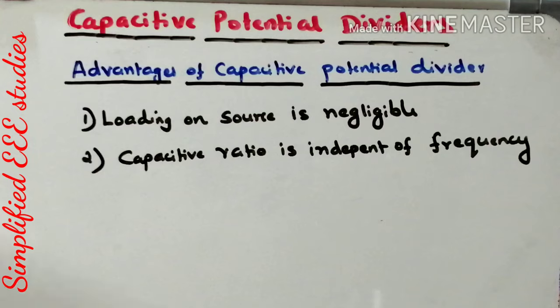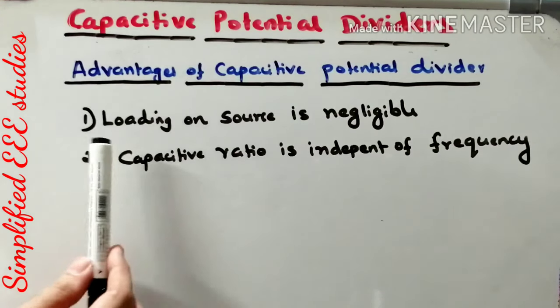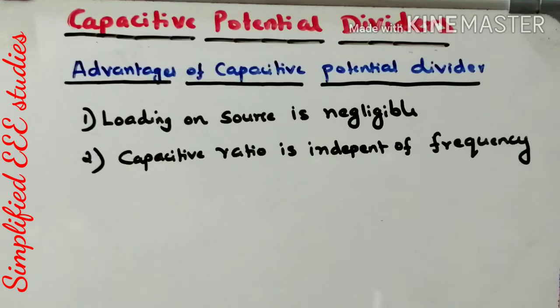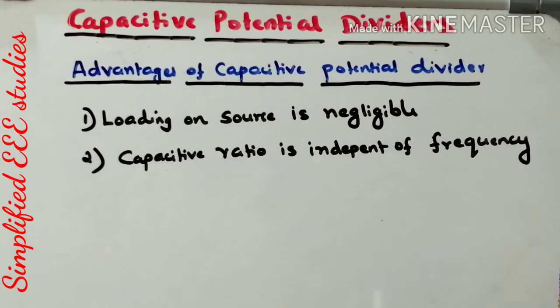Now let me outline some advantages of Capacitive Potential Divider. Number one: loading on the source is negligible — the meter will not consume any power from the source. That is one of the major advantages. Furthermore, the Capacitive Ratio will be totally independent of frequency — it is 100% independent of frequency. While doing the design, the frequency effect will be negligible. That is another advantage of Capacitive Potential Divider.